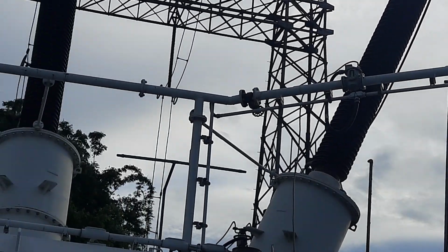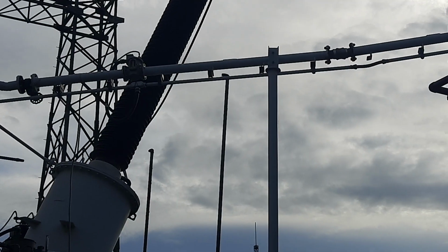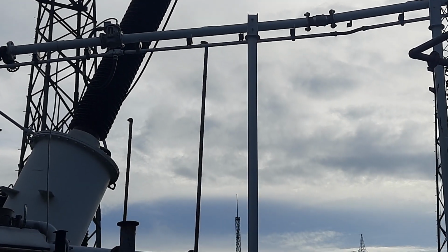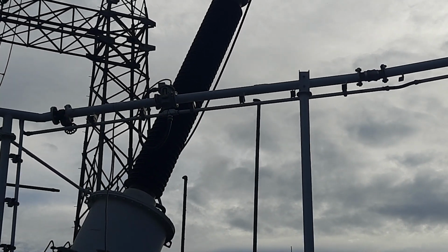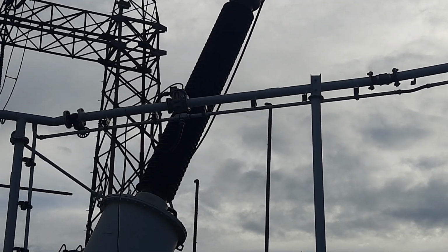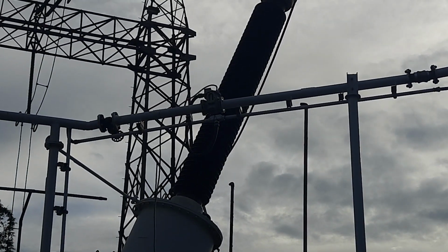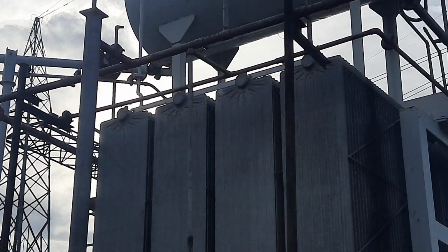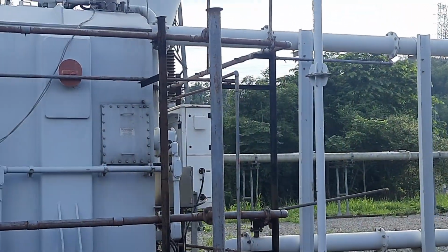And if the fault is severe or there is a sudden rise of oil, then the gases will keep on accumulating, and they will push the oil down further, up to a point that the second float also falls down a bit, due to which the magnetic contact will get actuated or shorted, and that will trip and disconnect your breaker. So this is how it works. And if you see from a bit of a distance, this is how it looks.